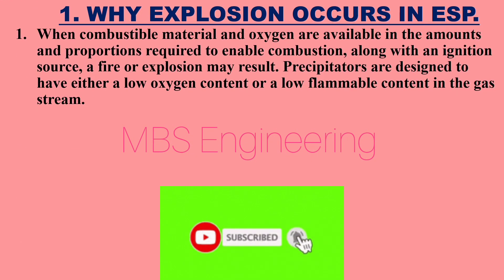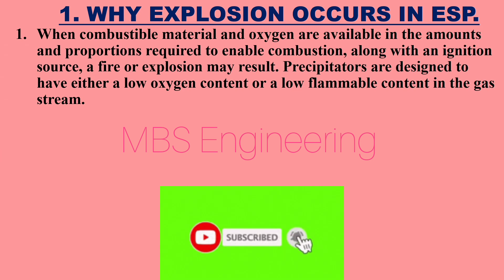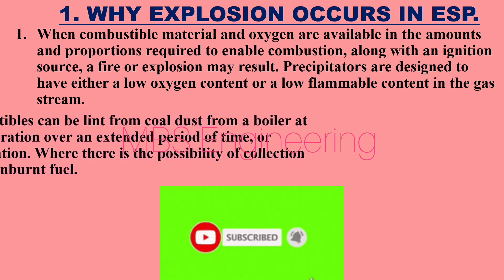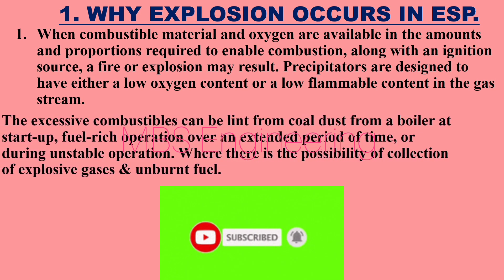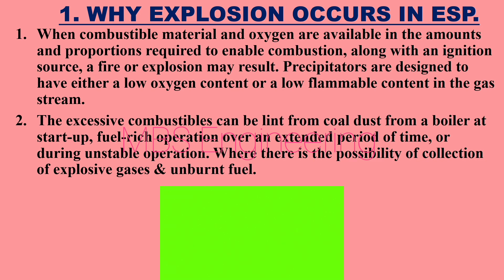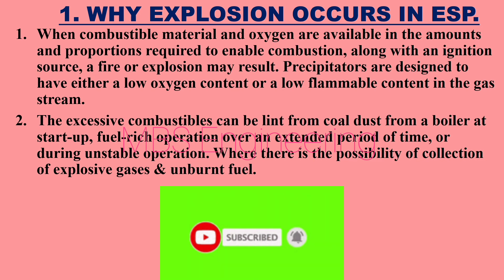Point 1: When combustible material and oxygen are available in the amounts and proportions required to enable combustion, along with an ignition source, a fire or explosion may result. Precipitators are designed to have either a low oxygen content or a low flammable content in the gas stream. Point 2: Excessive combustibles can be lint or coal dust from a boiler at startup, fuel-rich operation over an extended period of time.